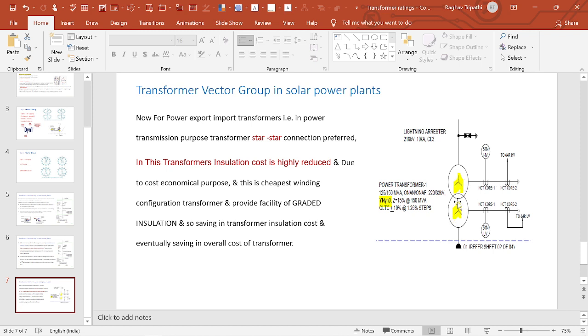For the power export/import transformer in power transmission, star-star connection is preferred. With star-star winding, the phase voltage is reduced by root 3 — phase voltage equals line voltage divided by root 3. The voltage stress on each phase is reduced by root 3, so insulation cost is also reduced by root 3. The transformer insulation cost is highly reduced, and star-star is the cheapest winding configuration among all winding configurations.